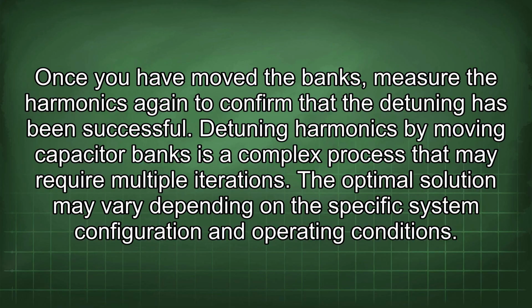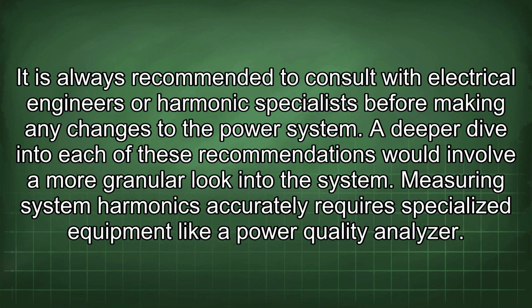Detuning harmonics by moving capacitor banks is a complex process that may require multiple iterations. The optimal solution may vary depending on the specific system configuration and operating conditions. It is always recommended to consult with electrical engineers or harmonic specialists before making any changes to the power system. A deeper dive into each of these recommendations would involve a more granular look into the system. Measuring system harmonics accurately requires specialized equipment like a power quality analyzer.